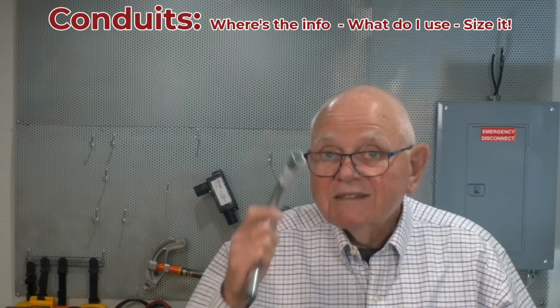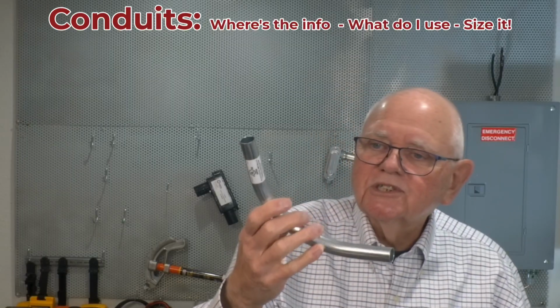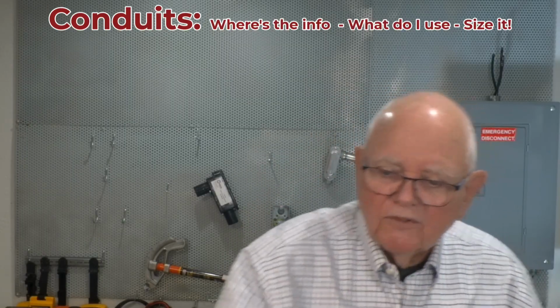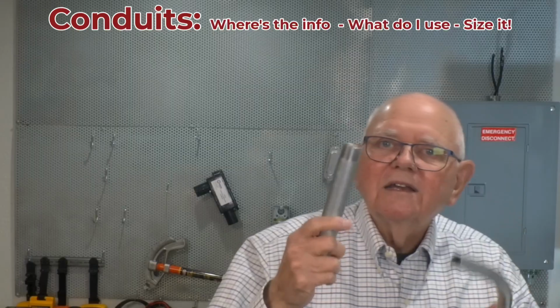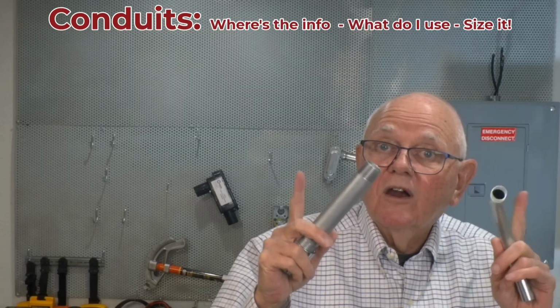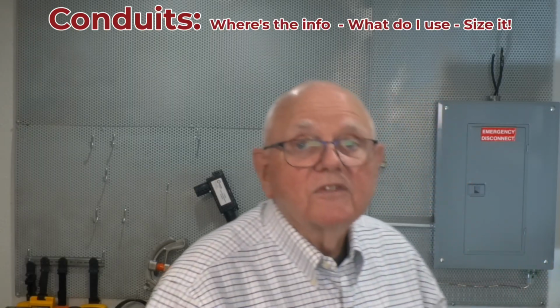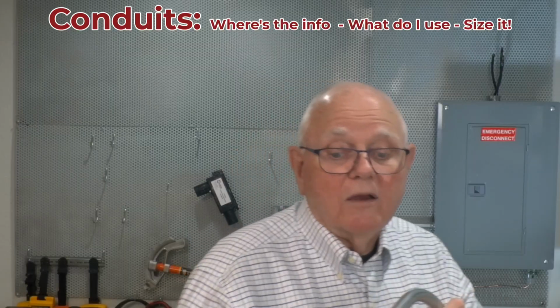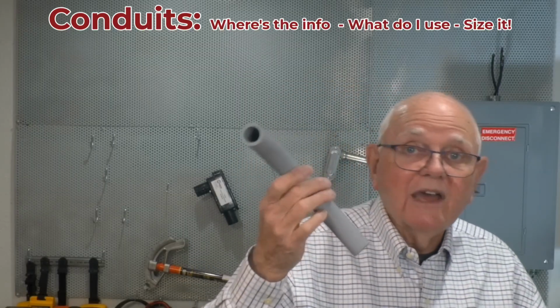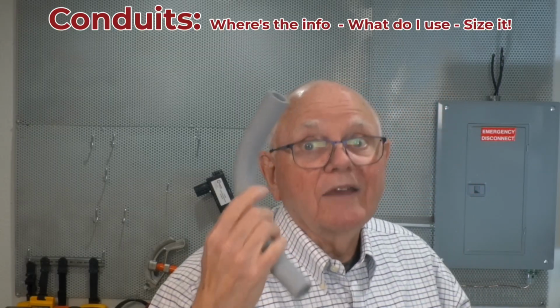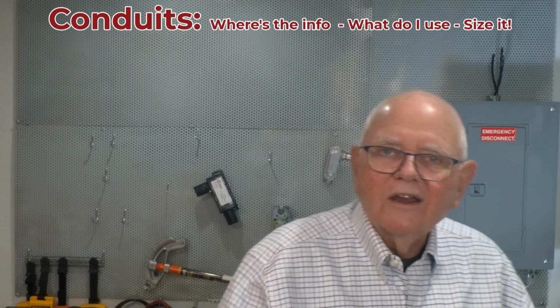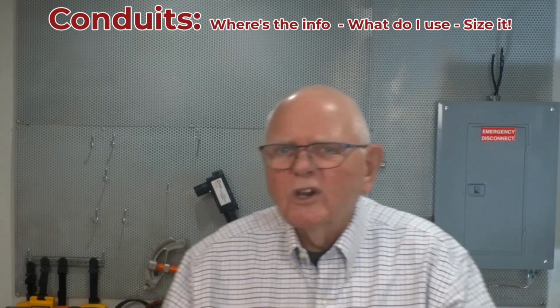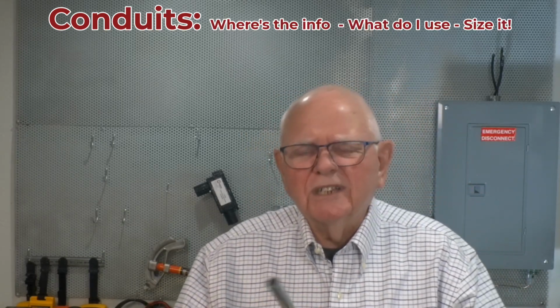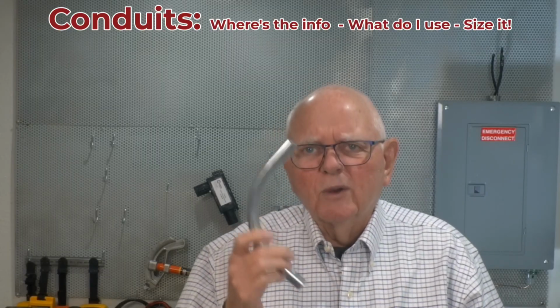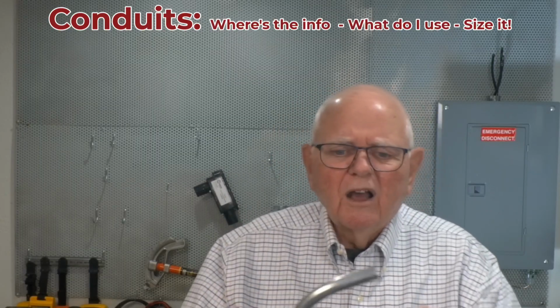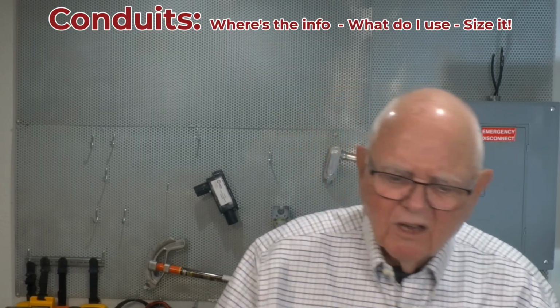The metal types, such as this metallic tubing or the rigid conduit, we're going to find that since they are metal, we can use them as the equipment grounding conductor as well. Obviously, the non-metallic type is not going to work. We're going to have to run the wire type equipment grounding conductor on the inside. But anymore, don't we typically, in most applications today, run that wire type equipment grounding conductor on the inside of the metal conduits as well?